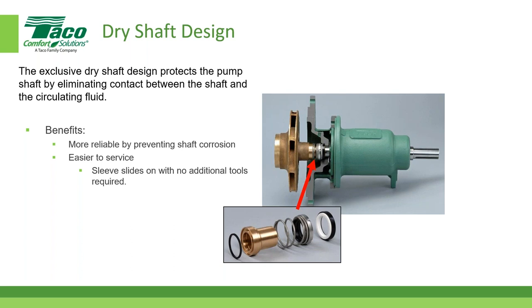More reliable by preventing shaft corrosion, and easier to service, right? So you can slide that sleeve off. So there's that sleeve I was talking about before that is a bronze, so it's a lot easier to get it on and off. Like I said, some people want stainless, but really that's something that you may want to get away from. So there's kind of the components of a seal right there, and that's the seat. So that's the one that sits right in there, pops right in there. You can see it mounted right there.